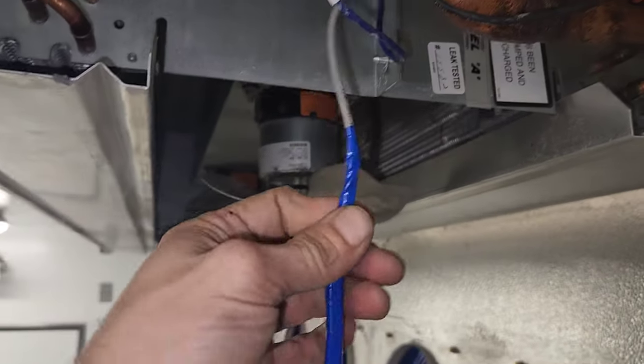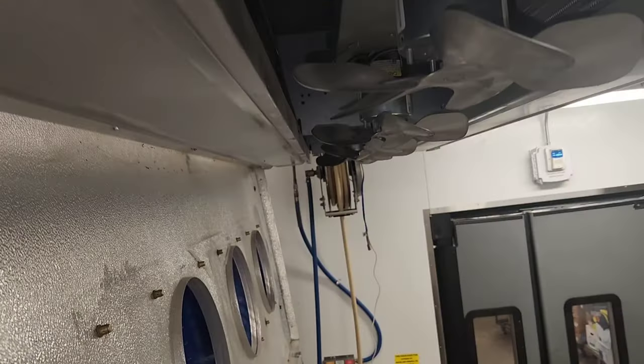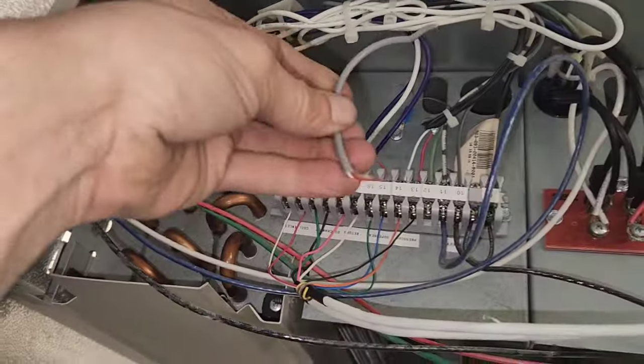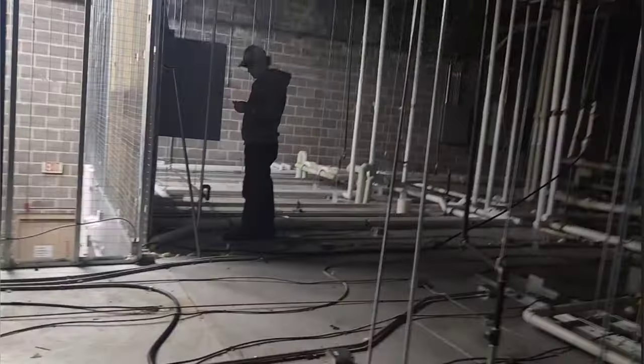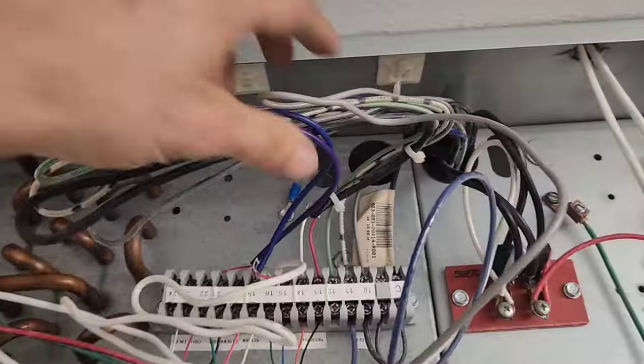All right. So this one here — the gray one. Well, then why does it say 'coil inlet'? I don't know. Okay, here's what I need to do — I need to make sure this is the right one in the RDM. So to test, I've disconnected what I think is probe four. I've verified it — it does say probe four on the RDM now. There was a guy up there who kind of surprised me, but once you get the one million little straps off, then you start.